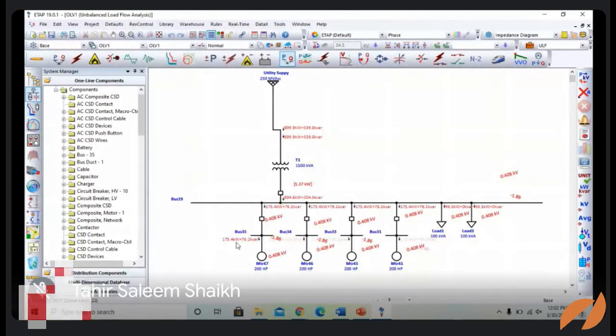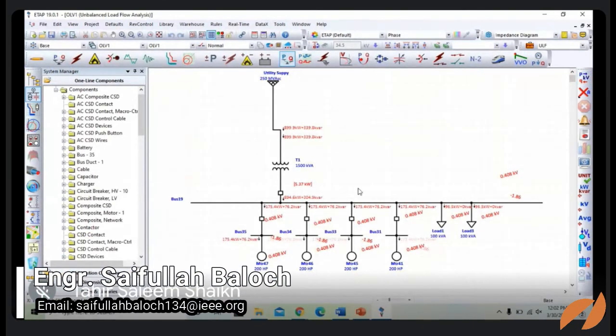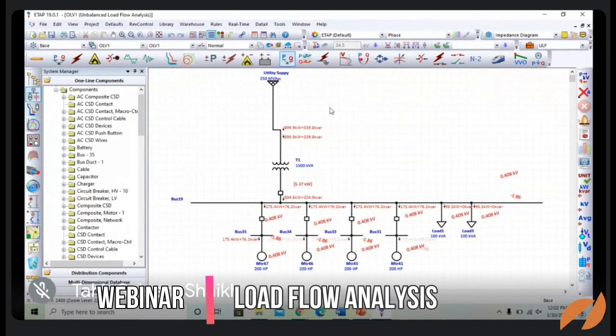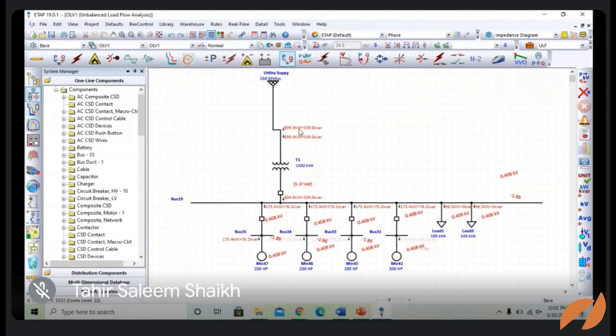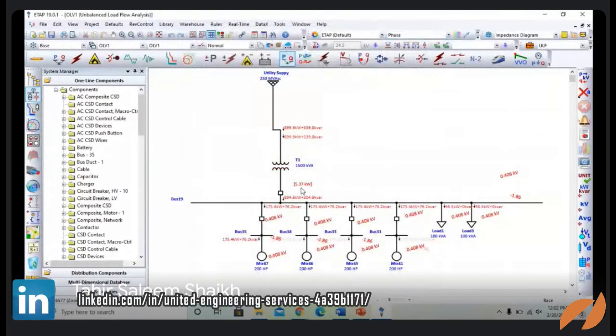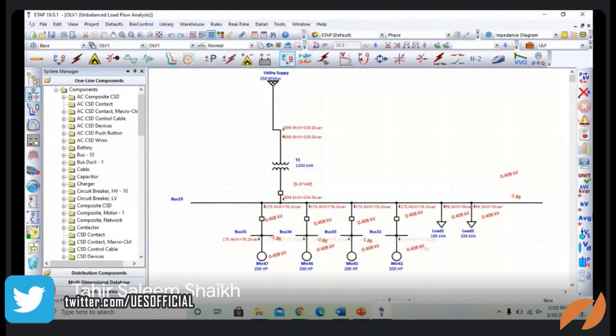Now you can see you have got these parameters over here. This is the power flow, 899.9 kilowatt plus 339.8 kVAR reactive. So this is the power flow from the utility company to the transformer. Now this 5.37 kilowatt is the power which is consumed over here. These are the losses. Let me just clear this.